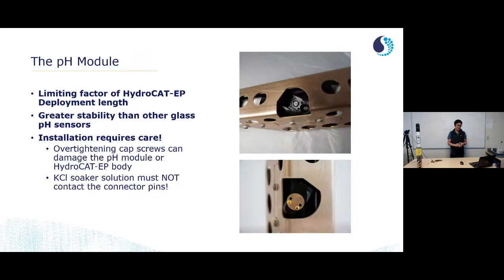That connector is liable to getting seawater into it, which can corrode the pins on the female connector on the HydroCAT body and the male connector on your pH sensor. So we've built some fail-safes into that to prevent seawater from contacting the pins. On top of that, we now have these 2 screws that screw into the HydroCAT EP body. Do not over-tighten these. They're pretty small. You're liable to damage your instrument. The installation process is simple, but must be done correctly.